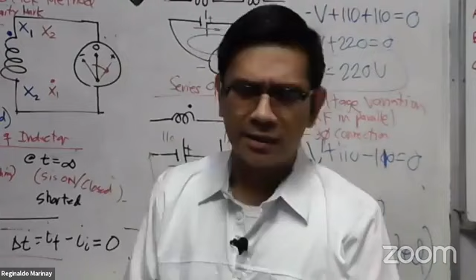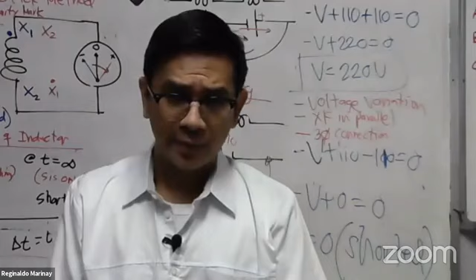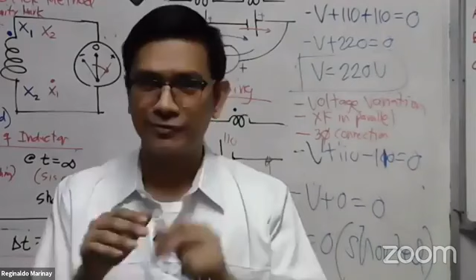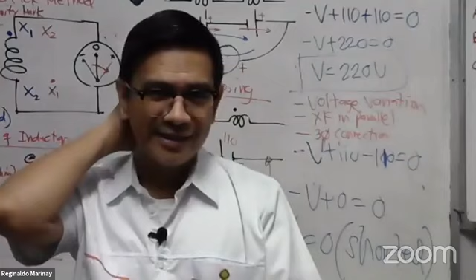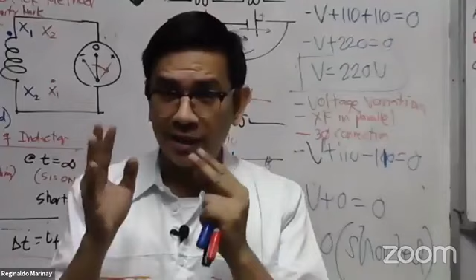Anyway, you can also see those diagrams in books, even in Google. You can type 'three-phase transformer connection' and you will see H1, H2, H3, X1, X2, X3. There you will see there is a consideration on the transformer polarity, because if you make a wrong connection, you will come up with a wrong output voltage. That is the effect.